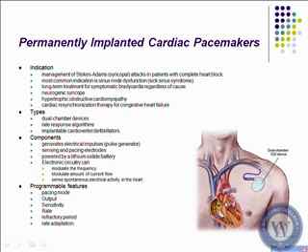Okay? The great thing about this is you have a great amount of capability with these too. They can be reprogrammed on the fly using different reprogramming devices. The downside to them is that you can reprogram them as well by accident. Okay? Usually not very often anymore because they're shielded, okay? But electrocautery is notorious for sometimes causing these pacemakers to basically reprogram themselves. Some of the new manufacturers are saying that, well, that doesn't happen anymore as much. But you know what? Every time you read the literature, what does it say at the end of the literature? Make sure that you check every time that the pacemaker is functioning before discharge from the hospital recovery room.